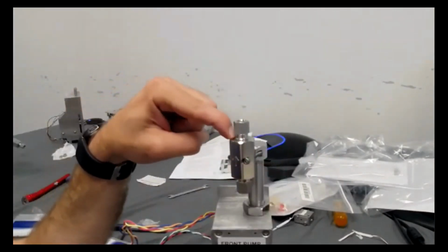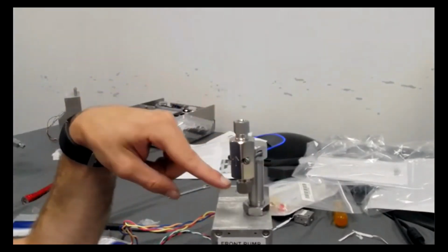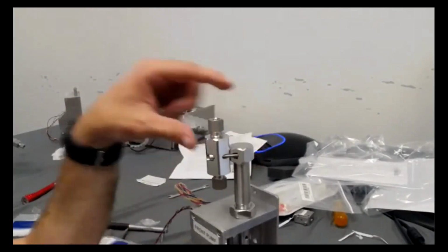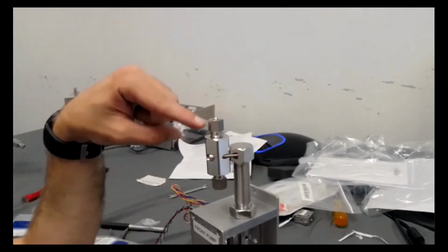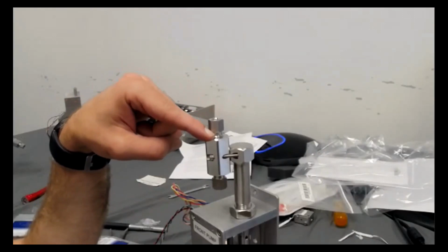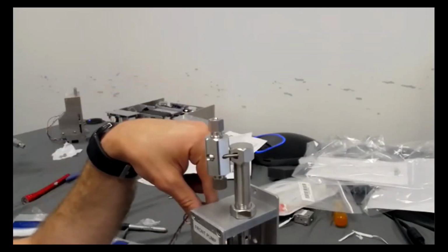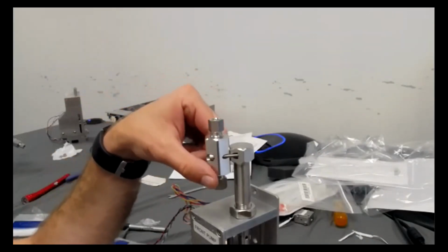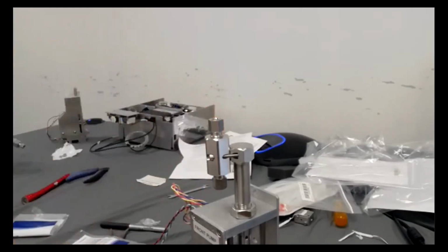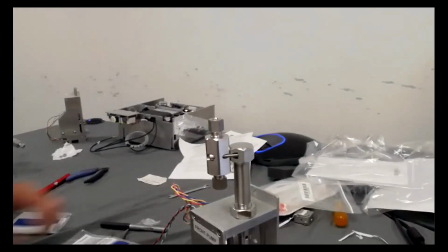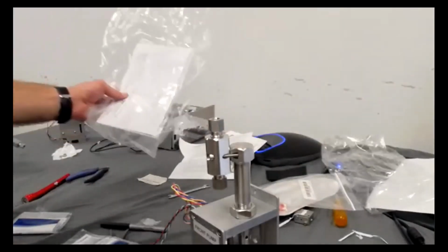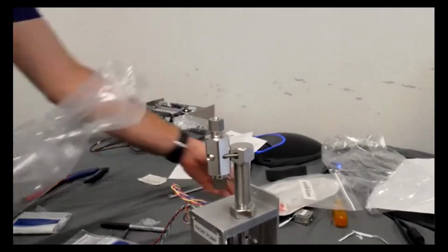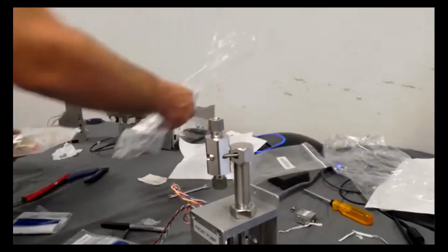If you notice leaking coming out of these threads, either top or bottom, or leaking coming out through the side, that could be an indication that you have a check valve that's stuck closed. Or, you just don't have something tight enough. So there's that, there's flushings that the PM instructions advise you to do. But I don't want to waste your time by doing a lot of talking about that stuff. I would just say to read the instructions that come.